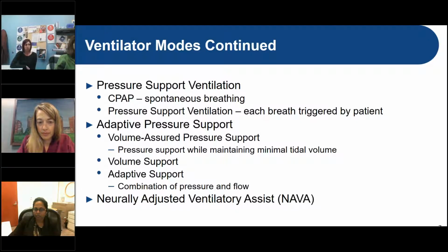The adaptive pressure support, in terms of different modes used, would be volume assured pressure support, where there is a set volume and the pressure support will vary to ensure that that minimum tidal volume is delivered. Volume support acts the same way. We also have an adaptive supportive mode that will allow just one set pressure, and the volume of those breaths will change. We also have a newer mode of ventilation called neurally adjusted ventilatory assist, or NAVA ventilation.